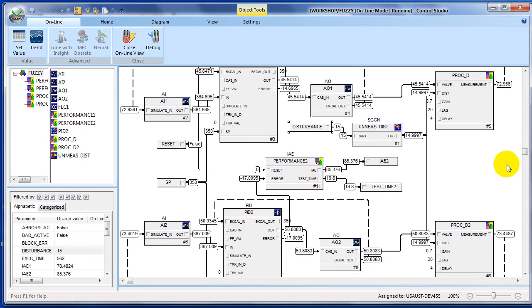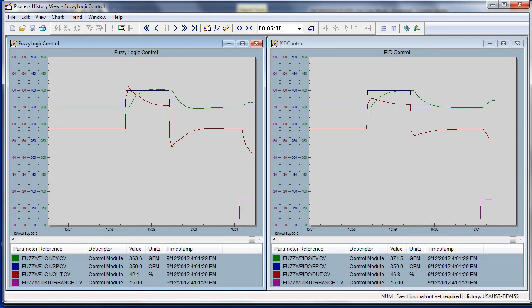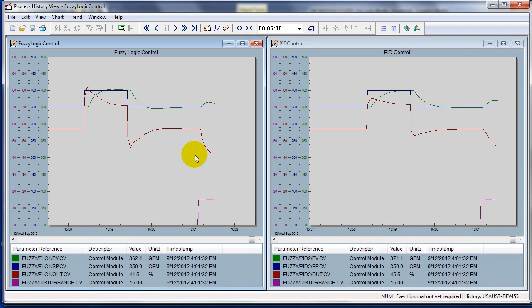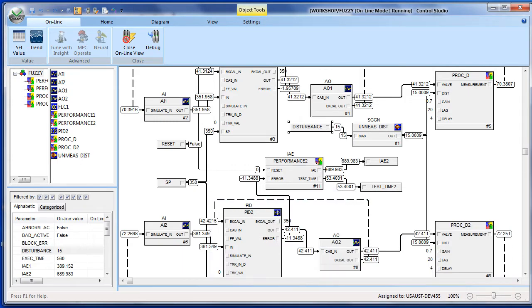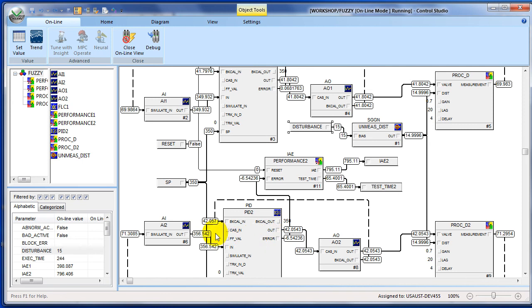As we can see, the disturbance has driven our process from set point in terms of the outlet temperature. Looking at the trend, the nonlinear behavior of fuzzy logic means we're able to counteract the disturbance much faster — attenuating that disturbance and getting back to set point in a shorter time frame. The behavior for unmeasured disturbance rejection is much more dramatic in comparing one to the other than what we saw for a set point change. We're getting back to set point much faster, and our integral of absolute error is quite a bit different between the two.